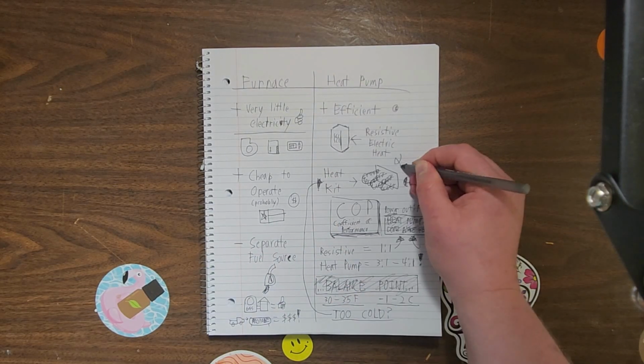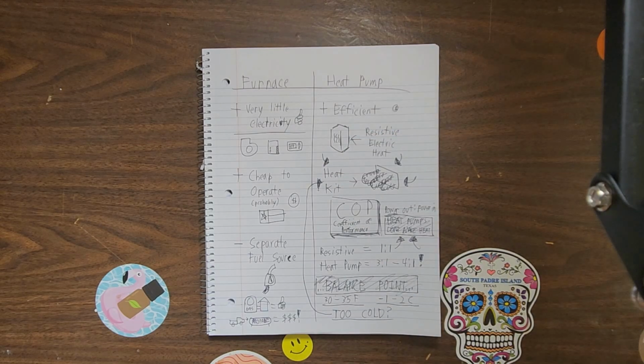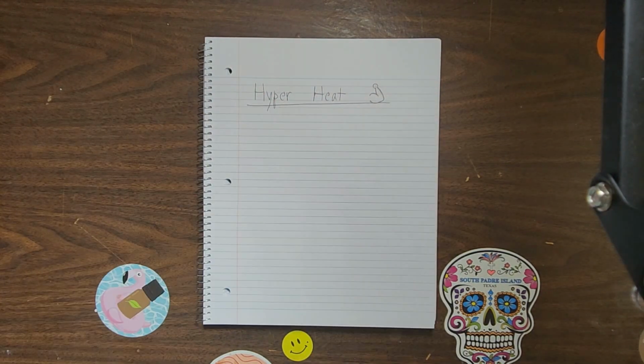So, how do you generally provide heat with the heat pump when it's below balance point? Well, by using an auxiliary heat source. Generally, this is by using resistive electric heat as mentioned above. This means that heat pumps, while incredibly efficient for heating in mild conditions, are nearly useless in sub-freezing conditions. And while there are some more efficient heat pumps out there, like hyperheat systems, most of them won't be able to heat below 30 degrees. Now there is another type of system called dual fuel systems, where a heat pump and furnace are combined.